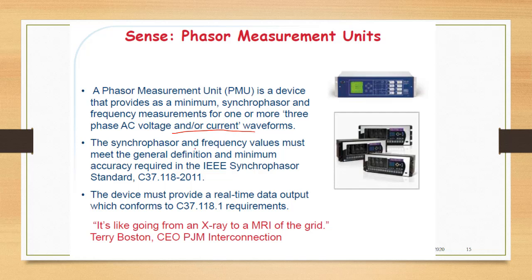The synchrophasor and the frequency values must meet the general definition and minimum accuracy required in the IEEE synchrophasor standard C37.118, published in 2011. The device must provide a real-time data output which conforms to C37.118.1 requirements. Terry Boston, the CEO of PJM Interconnection, says it's like going from X-ray to MRI of the grid when we are implementing PMU.